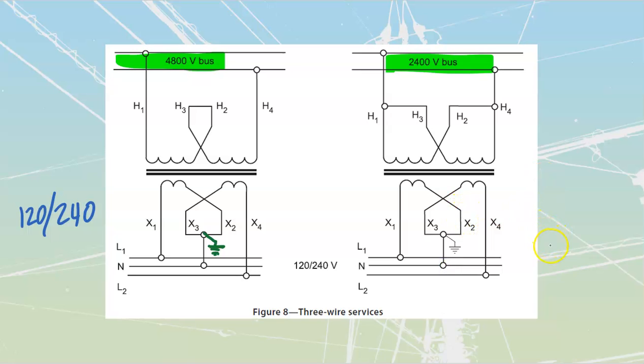Most cases, if I have a pre-made one, I will see a winding, and then it just goes down to another point over here, and we have another winding. They don't usually show the crossover in these types, and one of these is going to be labeled as my X1. The other is labeled as my X2, my low voltage 2. And then this point, my neutral, is going to be labeled as my XO.